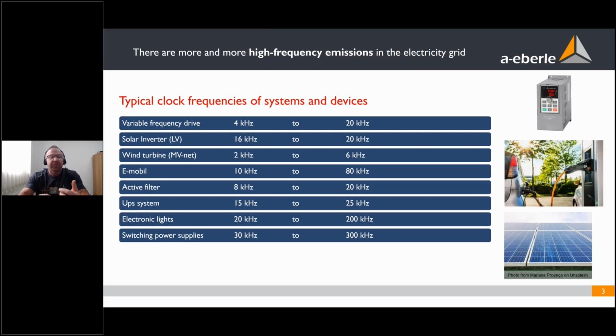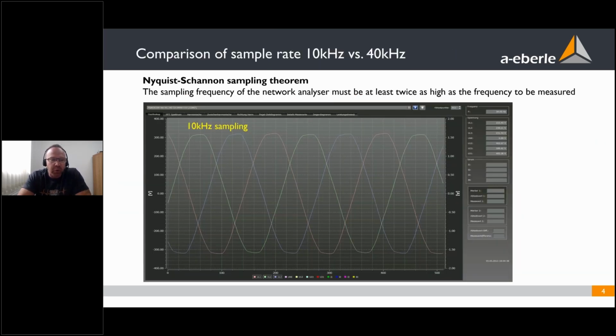And if you want to measure superharmonics, there's always a rule. The sampling frequency of a network analyzer must be at least twice as high as the frequency you want to measure. So any analyzer is limited to at most 50% of its sampling frequency.